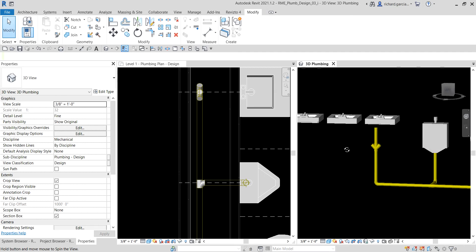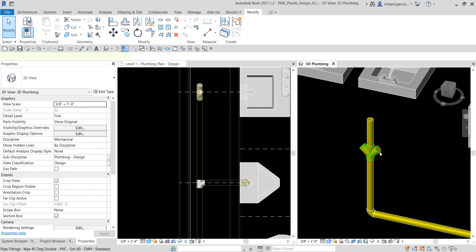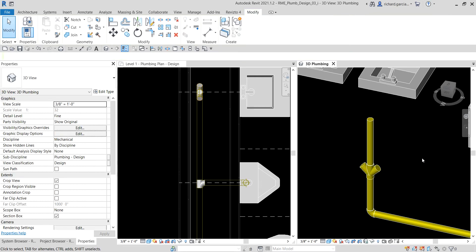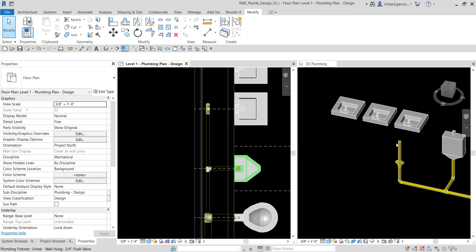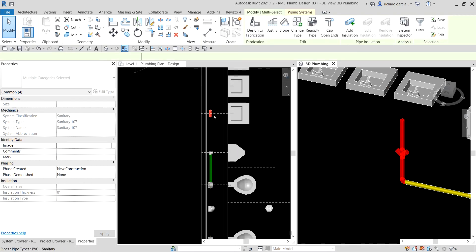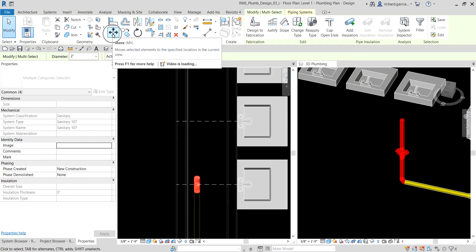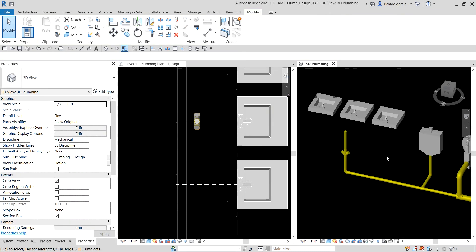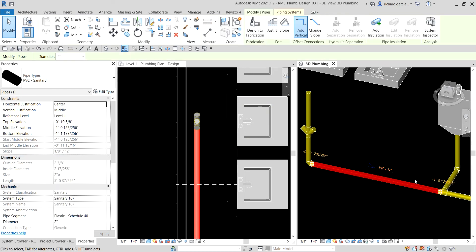I'll now change the offset of the pipe fitting to 6 inches. When typing the value, make sure to include the inch symbol — if you just type '6,' Revit will read it as 6 feet. After setting the offset, I'll move this whole pipe segment to align with the center lavatory using the move tool in the floor plan. Clicking the pipe confirms the slope is correct at 1/8 inch per foot.